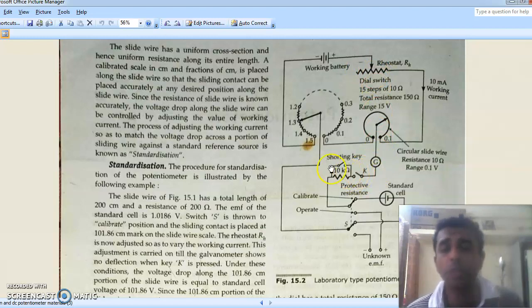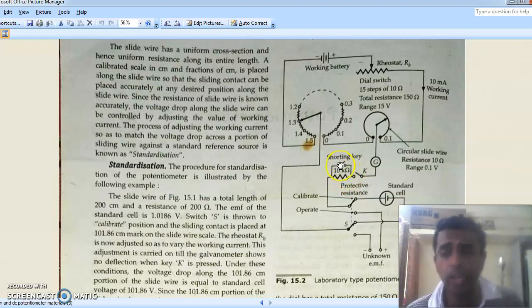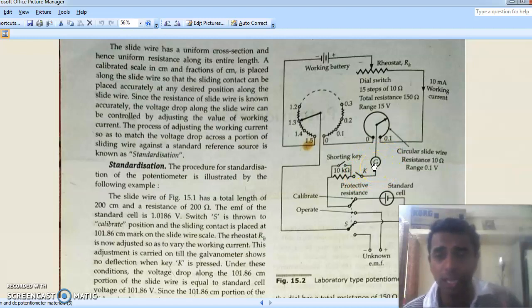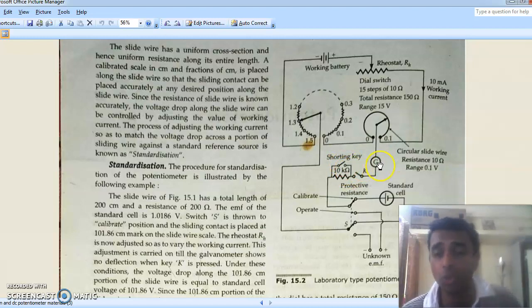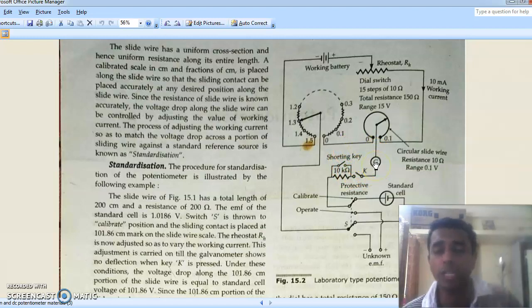Near the null deflection point, we can close the switch to short the 10 kilohm resistance. The advantage is that near the balance position the current flowing is very small, and by shorting this resistance the galvanometer sensitivity is increased. This effectively zooms in on the galvanometer vibration so we can achieve a perfect null deflection. After calibrating, we shift the switch to the operate position.